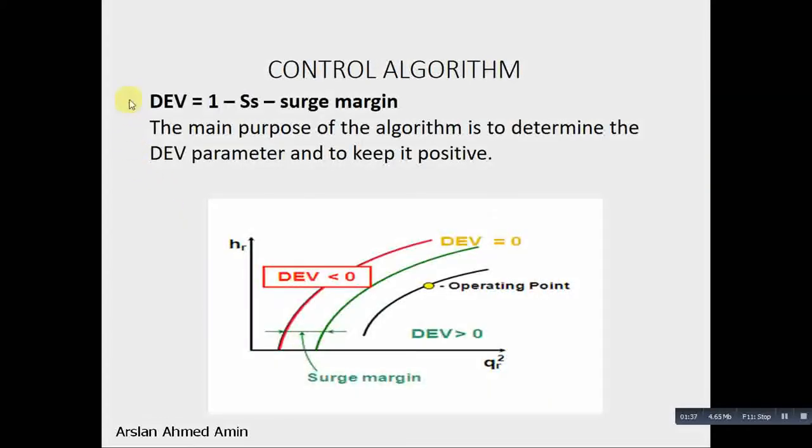Another parameter which is defined as deviation, which is equal to 1 minus Ss minus surge margin. A surge margin which can be 5 to 10%. The main purpose of the algorithm is to determine the deviation parameter and keep it positive.